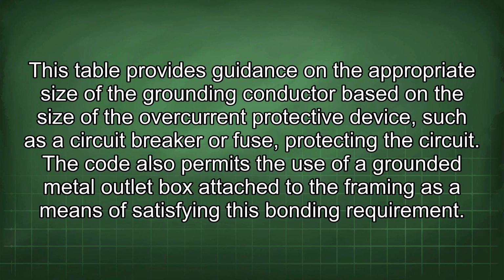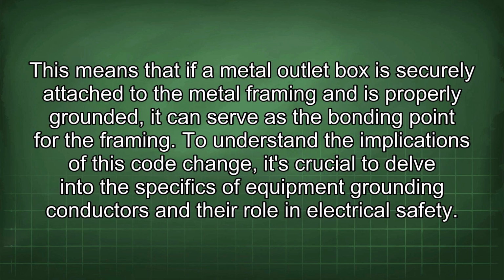The code also permits the use of a grounded metal outlet box attached to the framing as a means of satisfying this bonding requirement. This means that if a metal outlet box is securely attached to the metal framing and is properly grounded, it can serve as the bonding point for the framing. To understand the implications of this code change, it's crucial to delve into the specifics of equipment grounding conductors and their role in electrical safety.